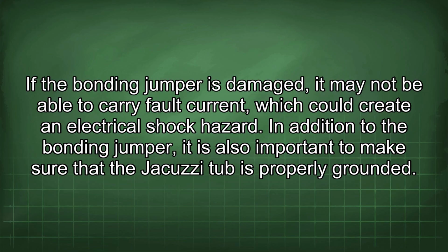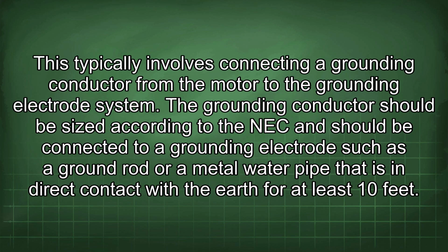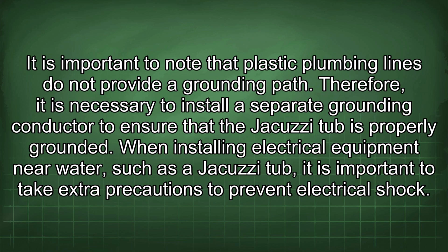In addition to the bonding jumper, it is also important to make sure that the jacuzzi tub is properly grounded. This typically involves connecting a grounding conductor from the motor to the grounding electrode system. The grounding conductor should be sized according to the NEC and should be connected to a grounding electrode such as a ground rod or a metal water pipe that is in direct contact with the earth for at least 10 feet. It is important to note that plastic plumbing lines do not provide a grounding path. Therefore, it is necessary to install a separate grounding conductor to ensure that the jacuzzi tub is properly grounded.